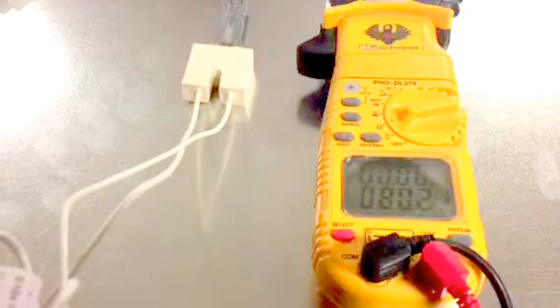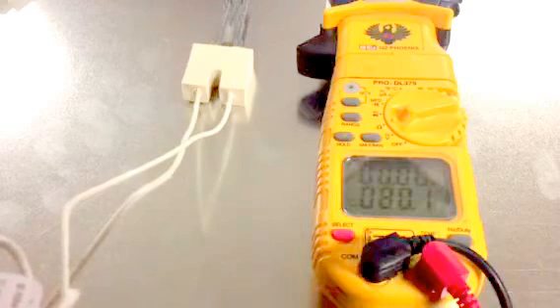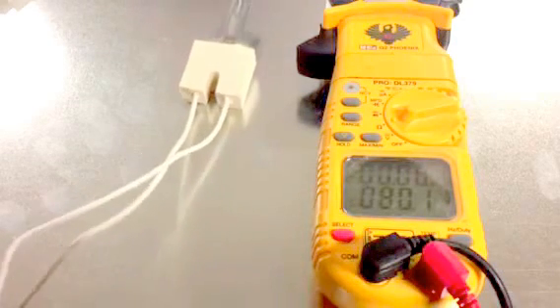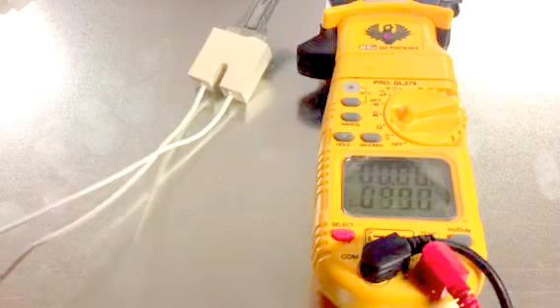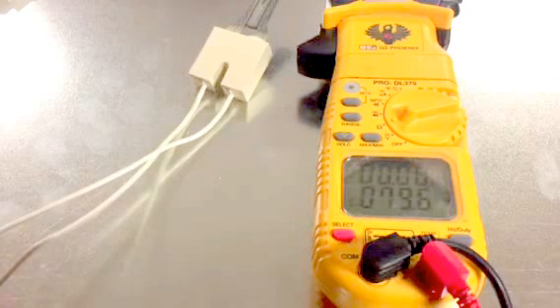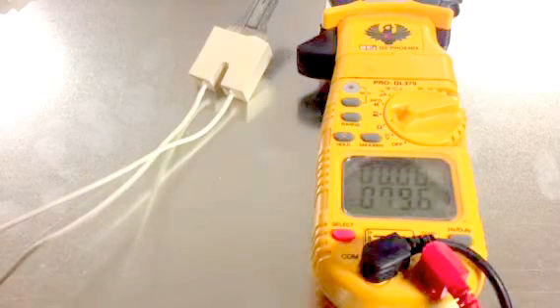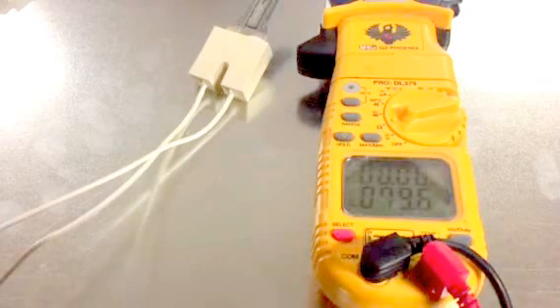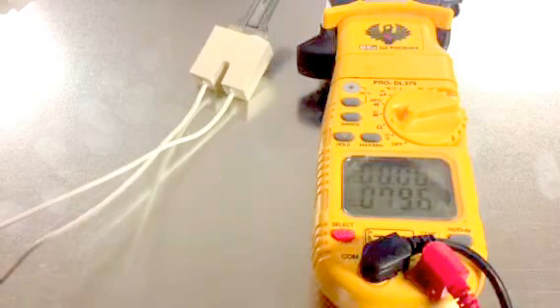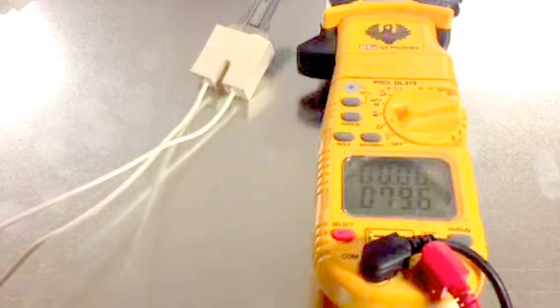As you can see there, we're 80.1 ohms. These should read, usually typically new, they'll read somewhere between 45 and 75 ohms. This one is brand new and it's already reading 80, that's still fine.